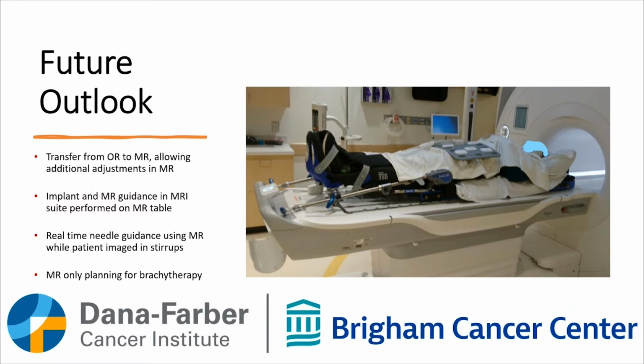Some of the barriers that come up initially: all of our implants are done via ultrasound, and currently there isn't a great MR conditional ultrasound alternative that can be used in the MR room. So what we do to date is perform the implant via ultrasound in our HDR suite, which is the previous image that was shown with the CT scanner. Once we are happy with the implant, we bring the patient through our department on this MRI table that you see here. We transfer the patient from the CT table or the procedural table, as imaged earlier, onto this table, and we bring them through our department under anesthesia and scan them, as Dr. Dyer had mentioned, for our planning scans.